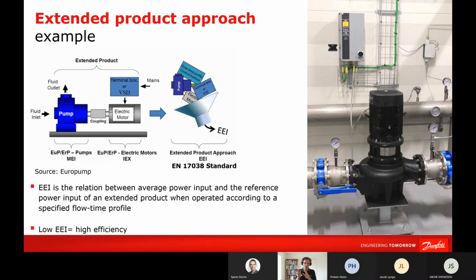We compare the result with a reference we get from the standard, and that of the motor system consisting of motor and variable speed drive, and we combine that with the data of the pump, and for a specific flow time profile, we can determine then the energy efficiency index. And you see, for calculating the motor system, we use the IEC 61800-9 standard, and then for the specific application, there are the respective standardization committees who determine how this is handled for each application. For example, there is the EN 17038 standard for the extended product approach for pumps.